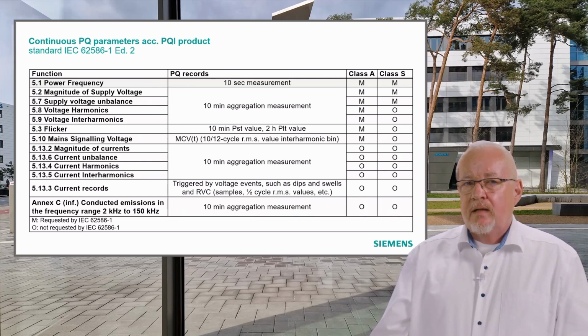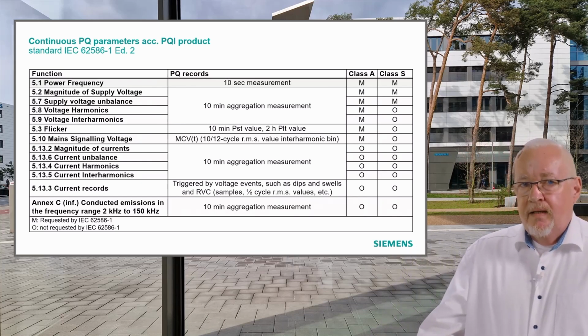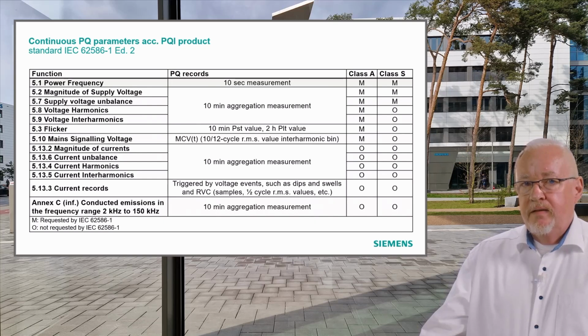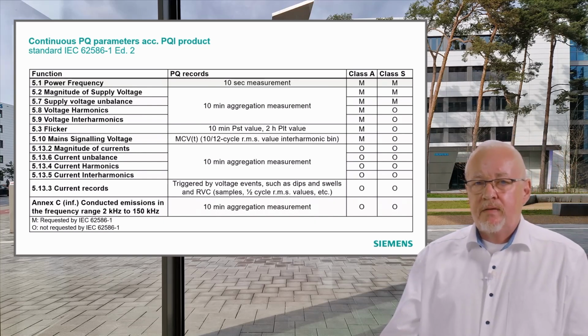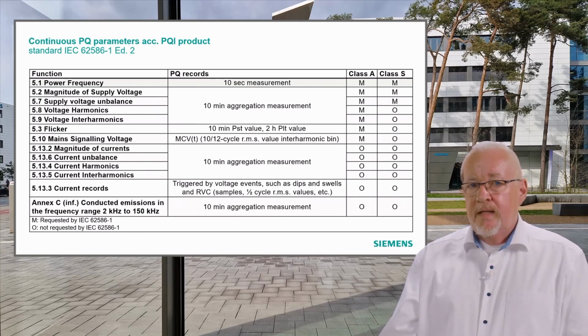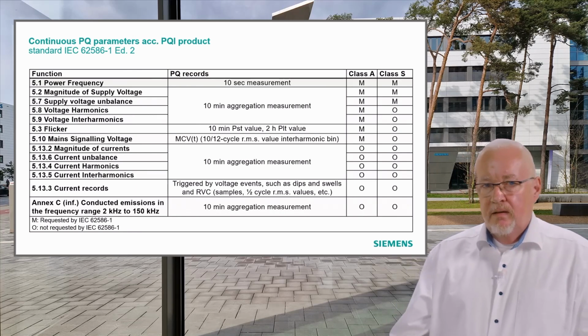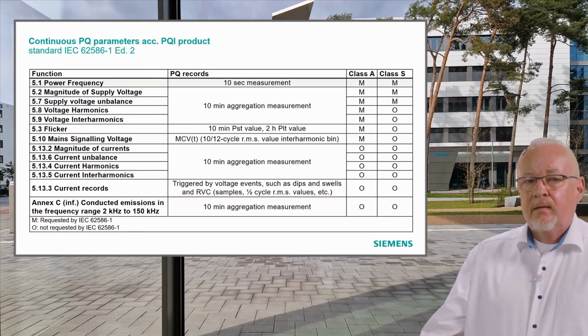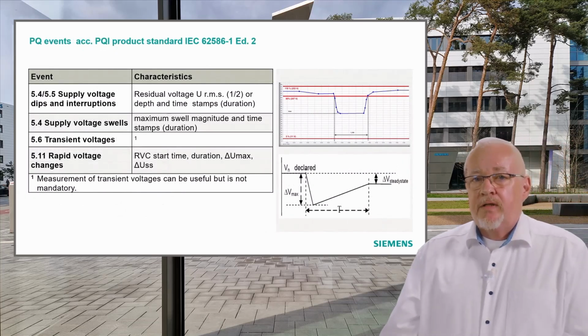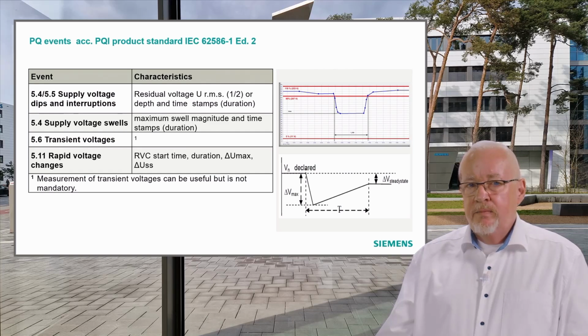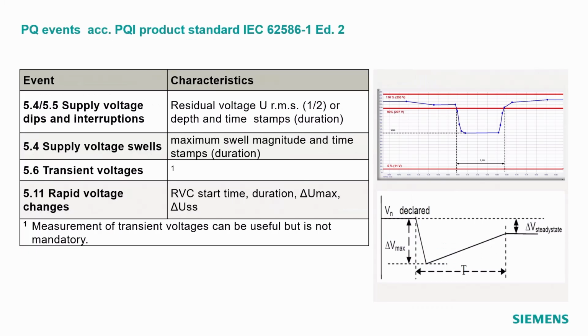Supply voltage dips and power quality events. For these phenomena, the logging of different event types is required. Supply voltage dips and interruptions, logging of residual voltage, U_RMS half or depths, and the time stamps for duration. See figure 1 later, as we are already on this slide here. Supply voltage swells, we have to log the maximum of swells magnitude and timestamps for the duration. Transient voltages, the measurement of transient voltages can be useful but is not mandatory. And rapid voltage changes, start time, duration, delta U max and delta U steady state are the parameters. You see two pictures on the right side.